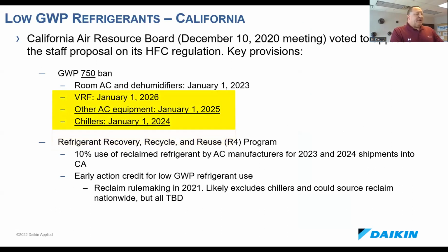The notable thing they've done now is go online with the chillers January 1, 2024, which is where the EPA is heading too. They want to stop the use of refrigerants in other AC equipment January 1, 2025, and they're proposing to allow an extra year for VRF systems. When we talk about other AC equipment, this is everybody's home air conditioners, every small packaged rooftop — basically the bulk of the 410A market — that California is aggressively pushing for a 2025 date.